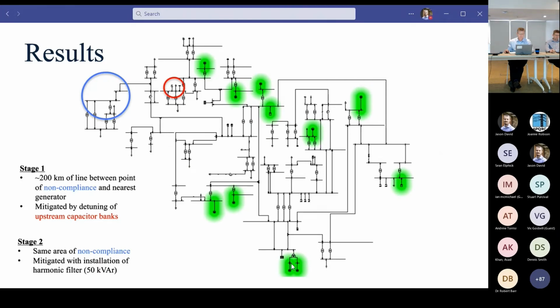And firstly, what we see is that without any mitigation, without any filtering, we hit a point of non-compliance that is 200 kilometres away, electrically, 200 kilometres of line between the point of non-compliance and the nearest generator, which is this point here. This is the point at which our harmonic voltages are the worst. And elsewhere and upstream from this point, voltage levels are sufficient, they're fine, not an issue whatsoever.